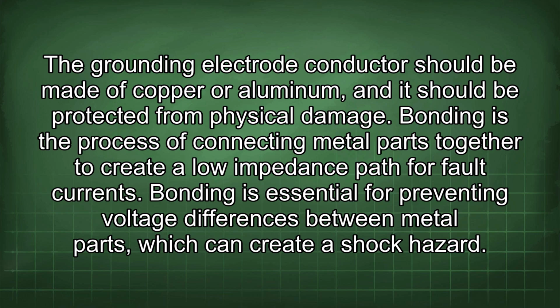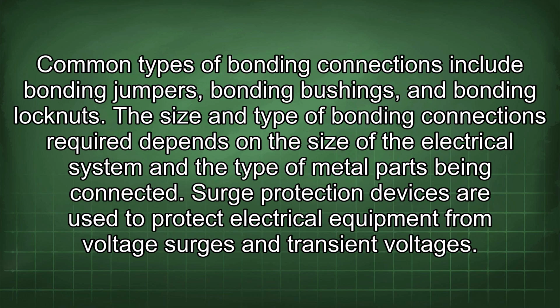Bonding is the process of connecting metal parts together to create a low impedance path for fault currents. Bonding is essential for preventing voltage differences between metal parts, which can create a shock hazard. Common types of bonding connections include bonding jumpers, bonding bushings, and bonding locknuts. The size and type of bonding connections required depends on the size of the electrical system and the type of metal parts being connected.